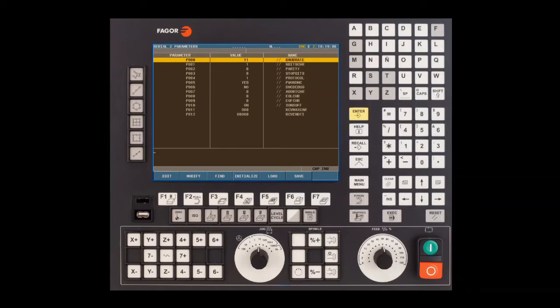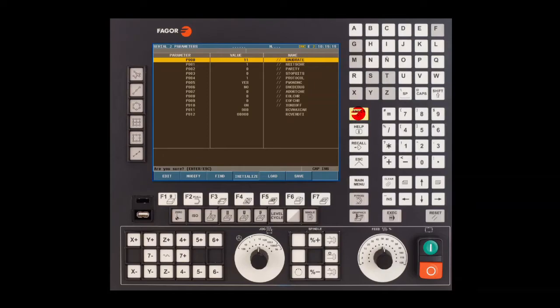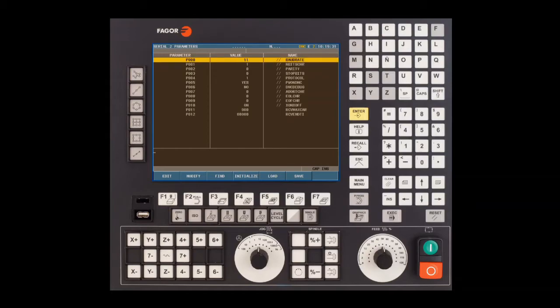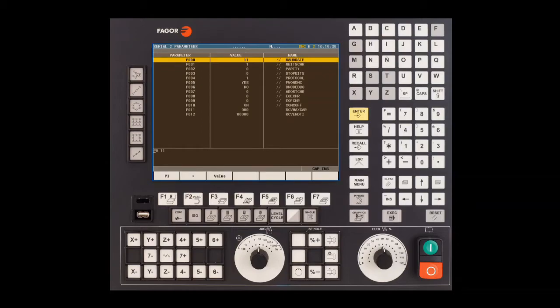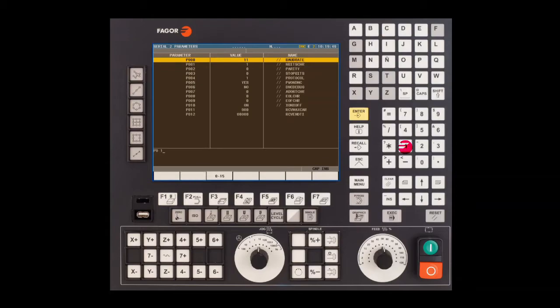Your configuration may be different to what I have currently. I need you to press initialize and you'll get a message on the lower left hand corner saying are you sure. Press the enter key to confirm that you've initialized the parameters. Older software will set the baud rate to 9600. You want to use the up and down arrow keys to make sure you have the baud rate selected parameter zero highlighted, press F2 for modify, cursor over and erase your current value which could be 7, and type in the value of 11 and press enter to confirm the new value.